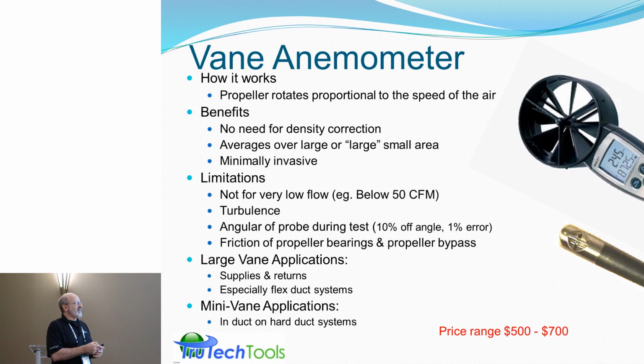And they're minimally invasive. They've designed the profiles very carefully. There are other manufacturers that make these, although the mini vane, I'm not sure anyone makes one of those besides Testo. That's unique. When you compare it to a hot wire, the hot wire is more accurate. It has higher sensitivity. Yes, absolutely higher sensitivity to changes in airflow. However, with the mechanical system that these require, they need enough flow pressure to get the vanes to turn, enough wind.